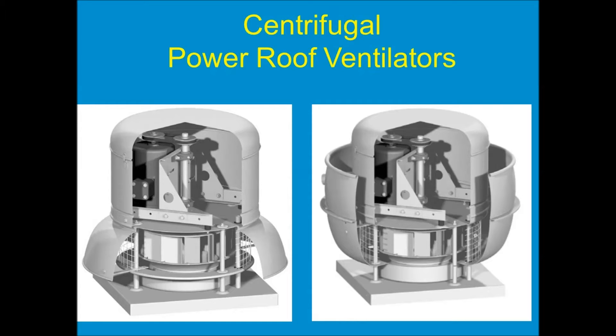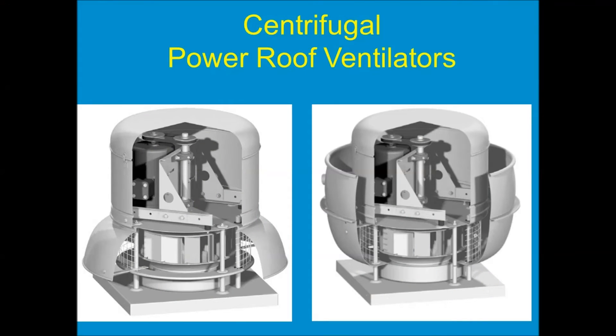In our part of the world, the northern half of the US, all things being equal it's better to specify the down blast type fan because it cannot fill up with snow and ice. The up blast fan, if it's not running over the weekend and you get snow or ice, it can fill up and create a little glacier that blocks the airflow. However, up blast is required for certain applications — grease exhaust kitchen fans must be up blast, laboratory fans must be up blast — because we cannot be blowing that air down onto the roof; we have to get it up and away from the building as soon as possible.